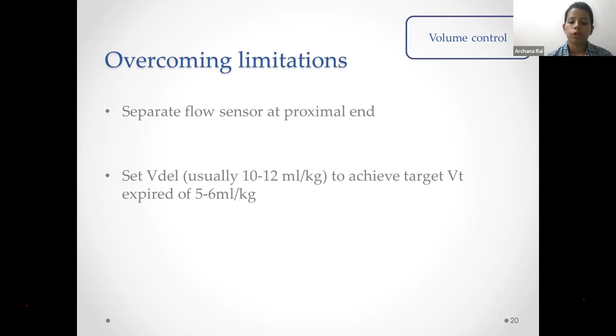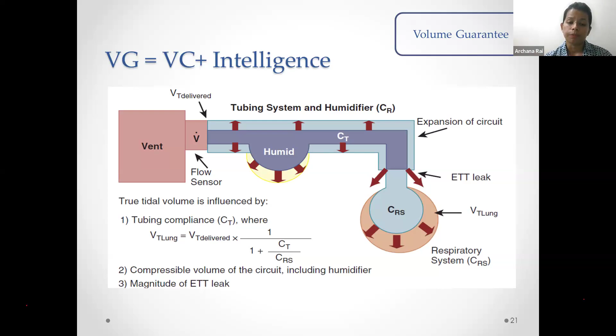another mode was brought into the scenario. It was volume guarantee. What is volume guarantee? It is basically volume control with some intelligence from the ventilator. What the ventilator does in volume guarantee is sense the V tidal delivered in the previous breaths or in the same breath, and then it manipulates the pressure to achieve a set tidal volume.